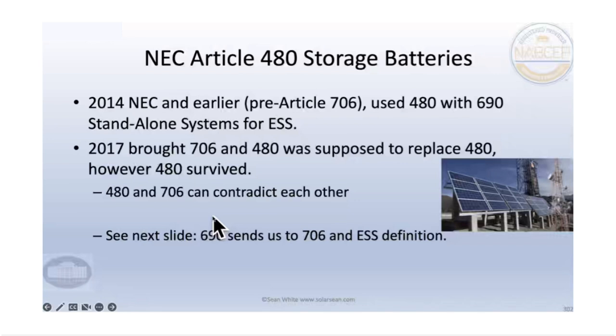Okay, thanks. And then the other thing you mentioned in the IFC, there was something about not storing flammable materials in the same area as a battery. Does that apply to residential too? I think it kind of complies with common sense. Yeah, if it's in a garage where there's cars or gasoline canisters. It does make common sense, but maybe that would be like some of that 110.26 stuff where it's got to be 3 feet back. You're not supposed to store things within 3 feet.